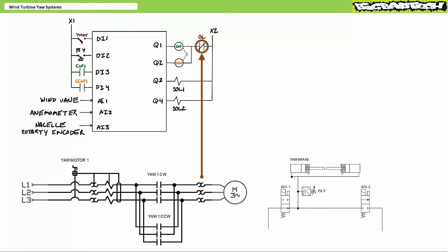It prevents either coil from being energized. This hardwired connection between a coil and normally closed overload contact ensures the overload has the last say about whether a particular motor is energized or not. You may or may not see this level of redundancy in a real-world implementation, but in my personal experience, it is most wise to include it.